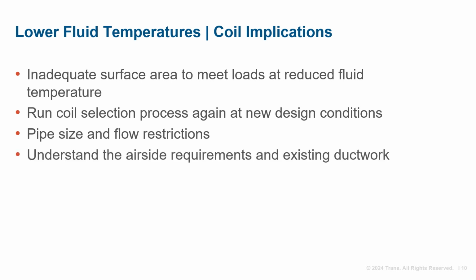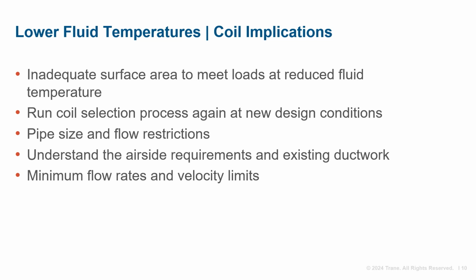At the zone level, based on a leaving air temperature, we need to know the volume of air required. If existing ductwork is being used, there may be a limit there. So the first question is, how much air and at what temperature is required to meet the design load? Once that has been determined, then we can begin to consider the coils. The coils themselves have minimum and maximum flow rates and velocity limits. So, if possible, modify coil inputs to identify those limits.